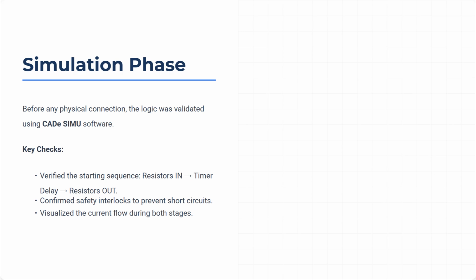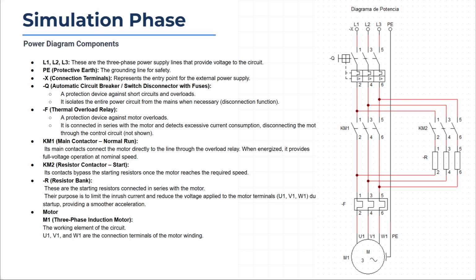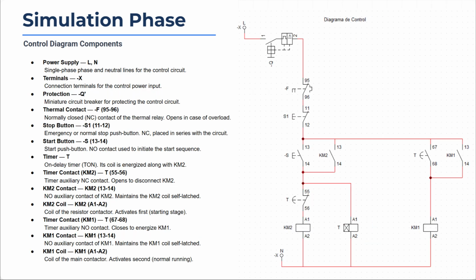Simulation. Before the physical assembly, we validated the logic in CADe SIMU. We verified the startup sequence, resistor on, timer delay, resistor off, and confirmed the proper safety interlocks. Power diagram. In the power diagram, energy enters through L1, L2, L3. Device Q is the main protective circuit breaker. Contactor KM2 connects the resistor R in series with the motor for reduced voltage starting. Afterward, contactor KM1 activates to bypass the resistor and feed the motor at full voltage. Thermal relay F protects the motor against overloads.